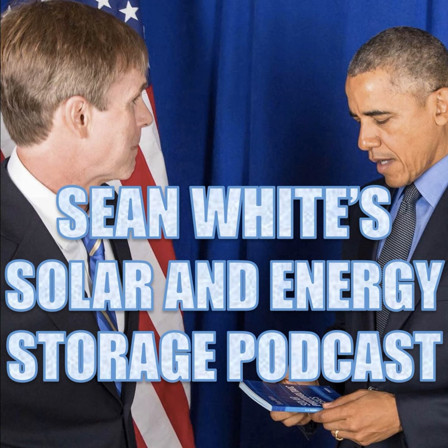A lot of times what happens is we have the energy that we need, and we need to increase the size of the battery bank because of efficiency losses, or how much you keep. So if we needed 4 kilowatt hours and we were going to lose 10%, or we could say we're going to keep 90%, then we take 4 kilowatt hours divided by 0.9, and we get 4.44 kilowatt hours. That's the math.